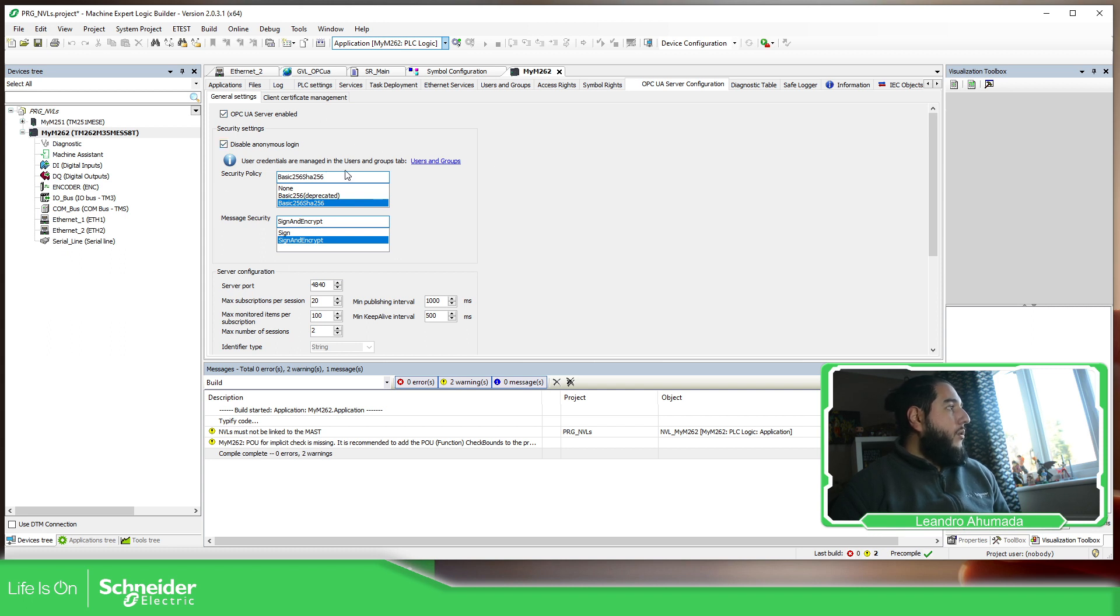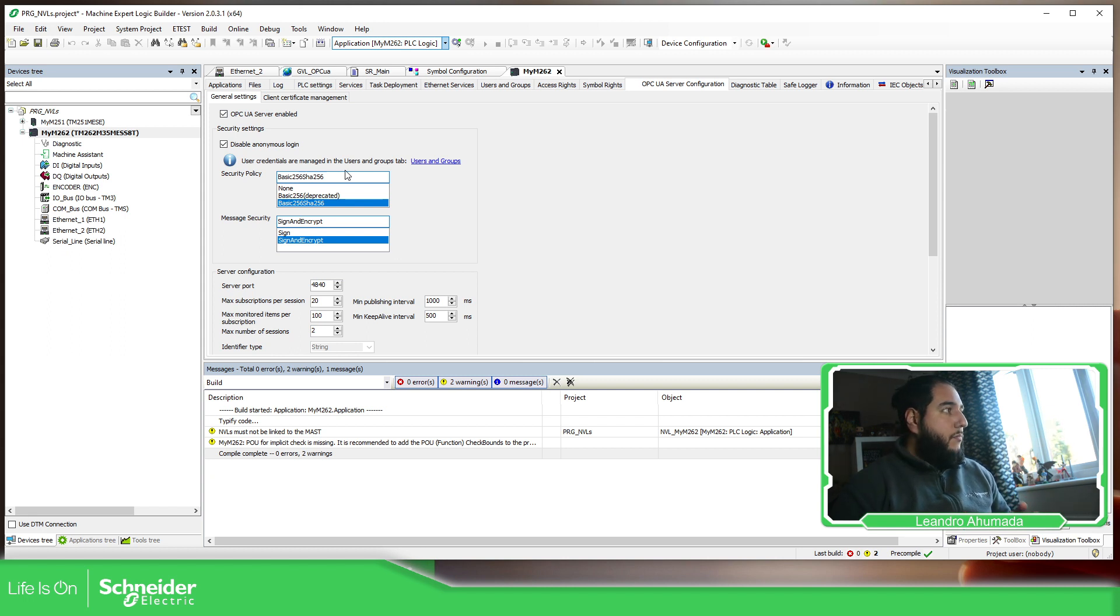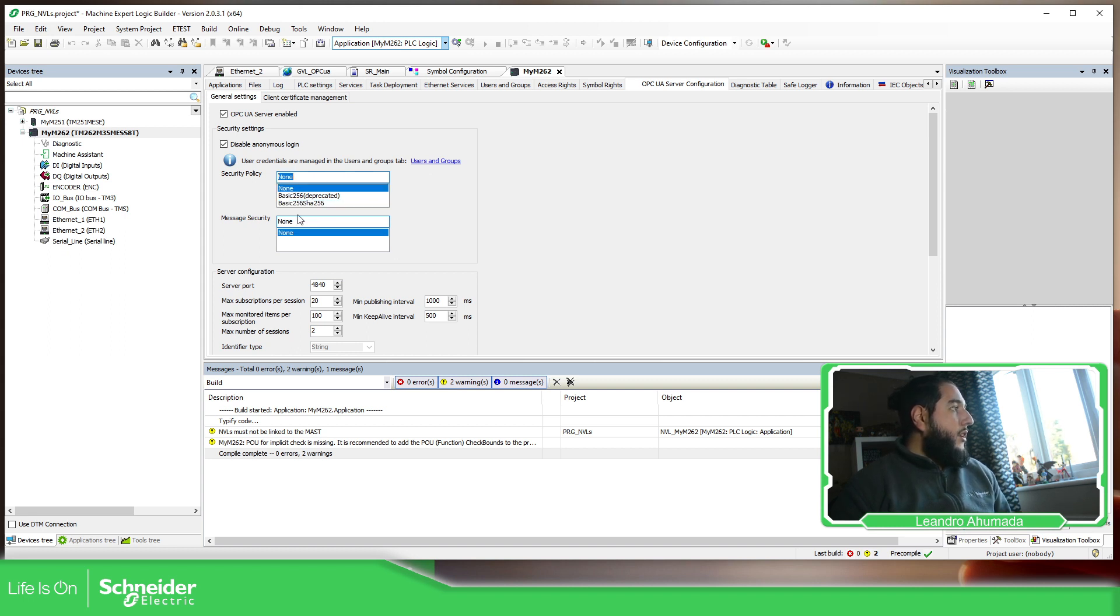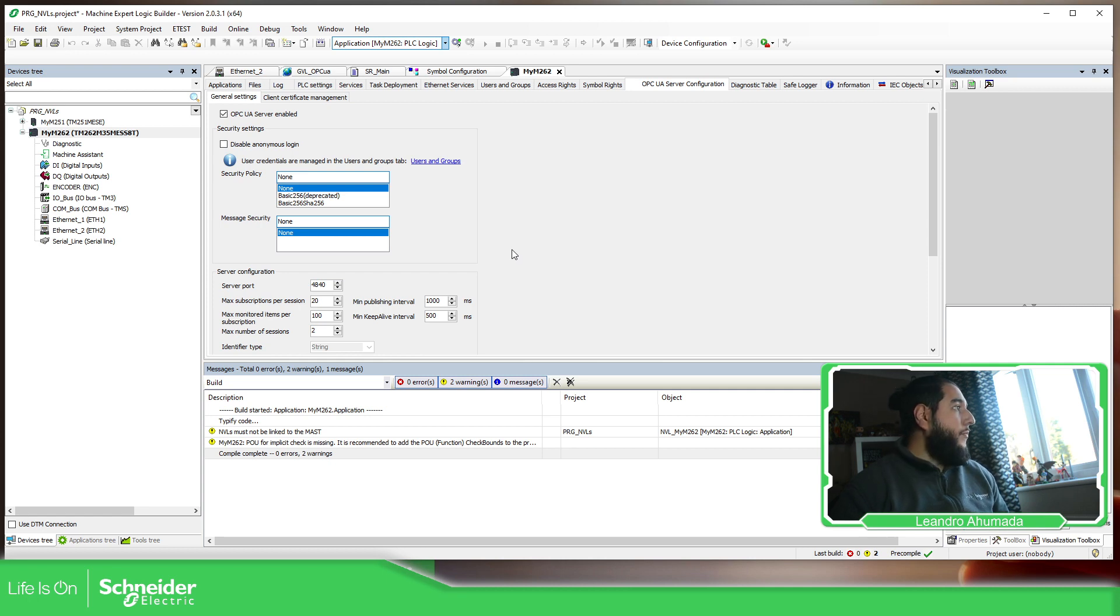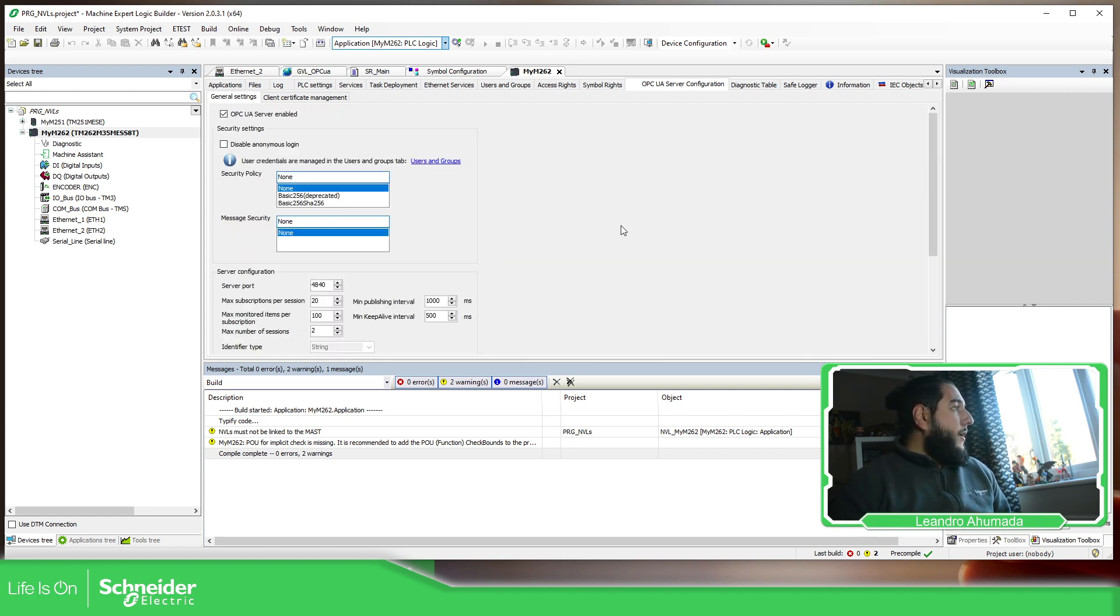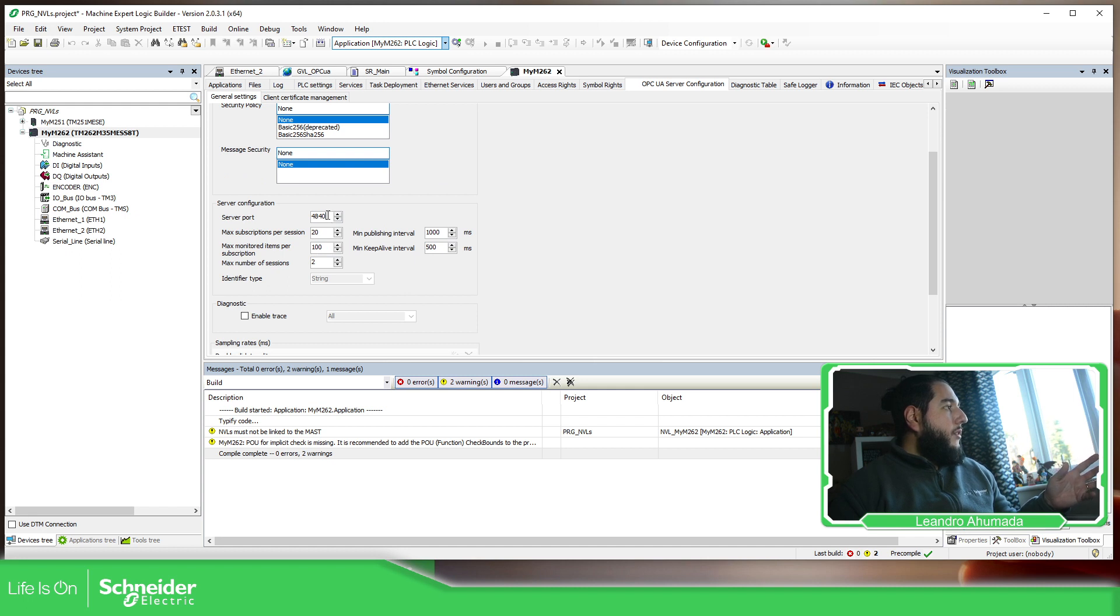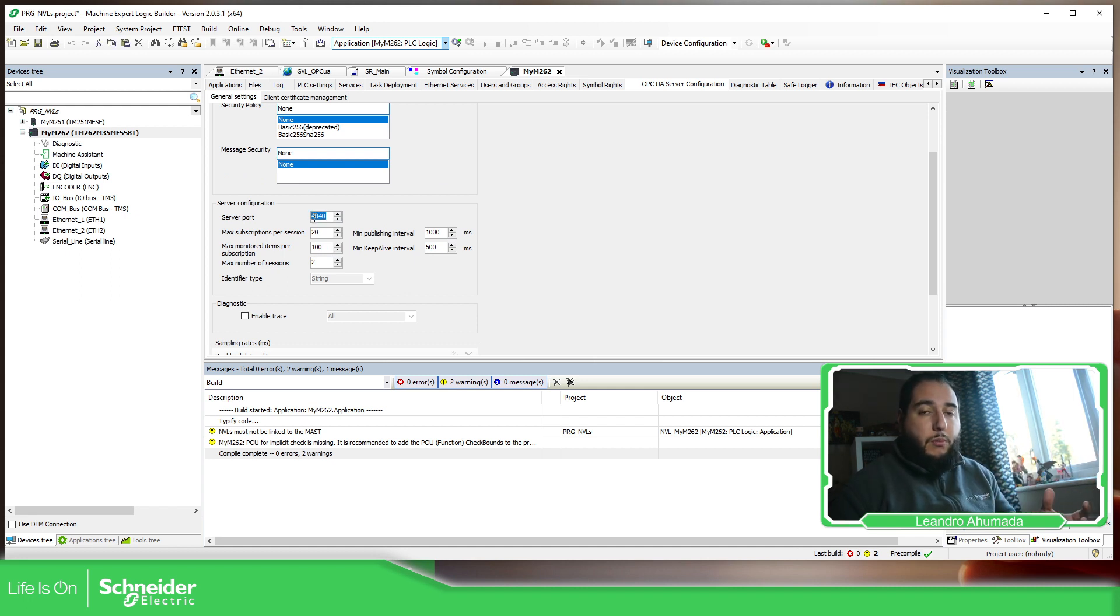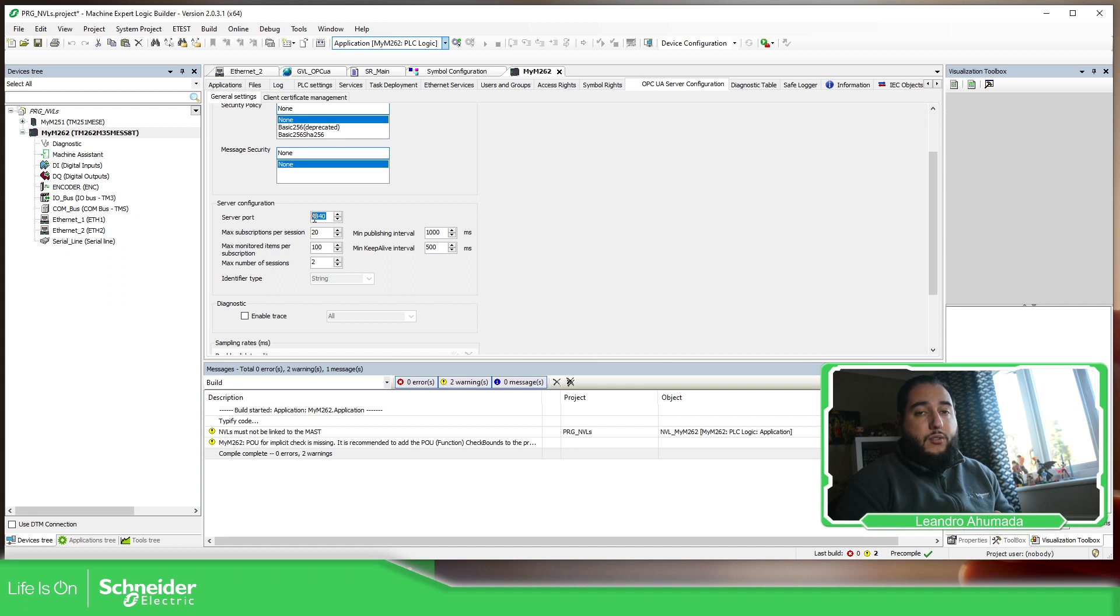And here we have the possibility to add more security in our communication. But in this first part, what I'm going to do is to not use any security, and I'm not going to disable the anonymous. So I should be able to login directly into the controller. The only important thing is this part of the sessions, but this will depend on your application. But the important thing is the server port, that is the one that we need to enable in order to open the OPC UA client.